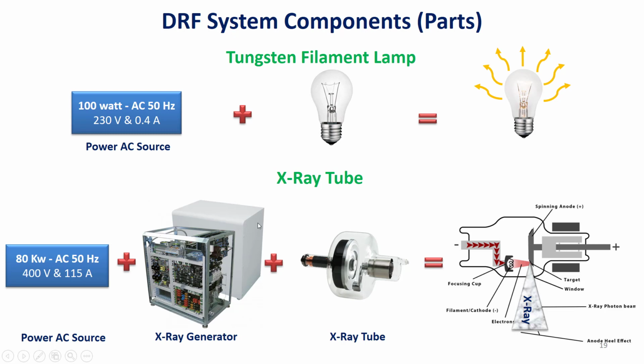So the first question comes to our mind: why do we need an X-ray generator and why can we not connect directly to the hospital power? To answer this question, we need to understand the requirements in order to operate an X-ray tube. An X-ray tube needs a current source, which is usually for the cathode filament, to generate an electronic cloud. Then a strong electrical field between the cathode and anode sides of the X-ray tube is created using a high voltage source, which directs the generated electrons towards the anode with a high speed. This high voltage source must be a DC voltage source with a range of 40 up to 150 kilovolt.